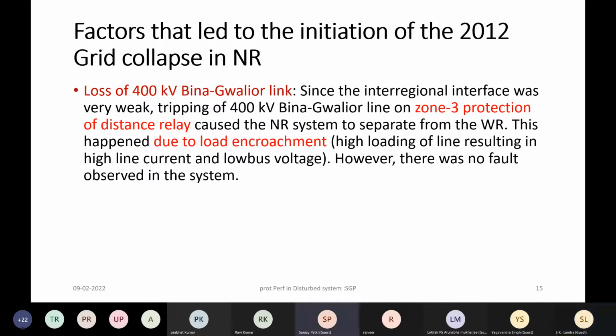I gave you as an illustration the example of the 2012 grid collapse. This is what was the summary. Basically, there was a loss of the 400 kV Bina Gwalior line. This is basically a line which was an interconnection between the western region and the northern region. And this line operated on zone 3 of the distance relay due to overdrawal, and this resulted in separation of the northern region and western region.